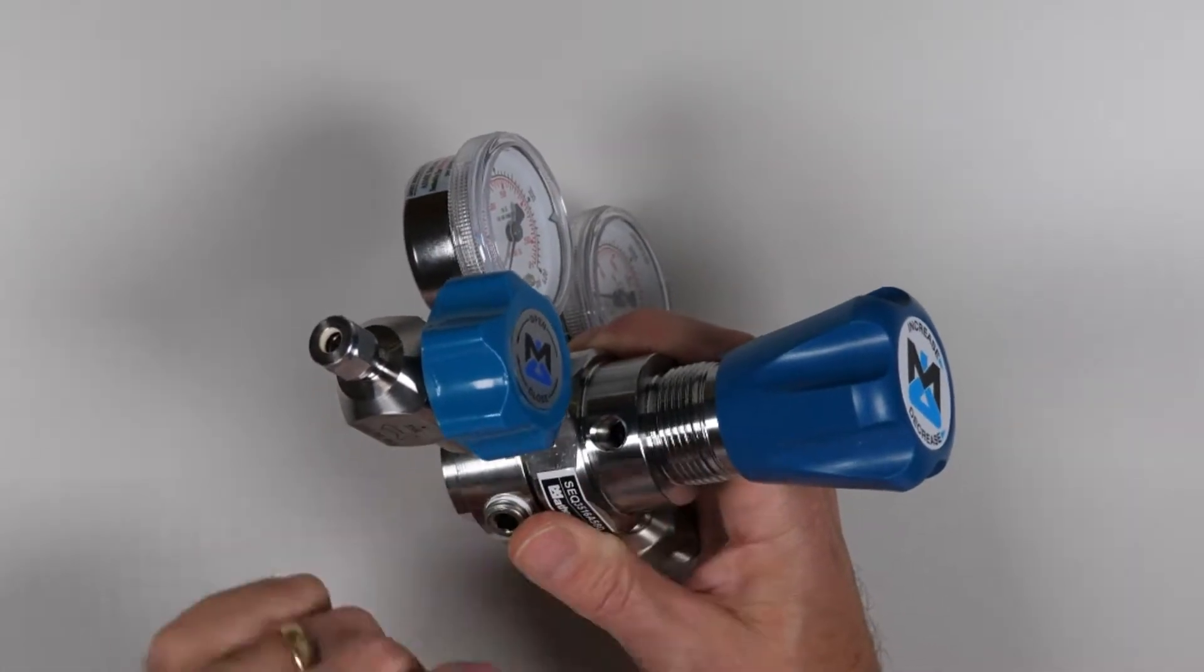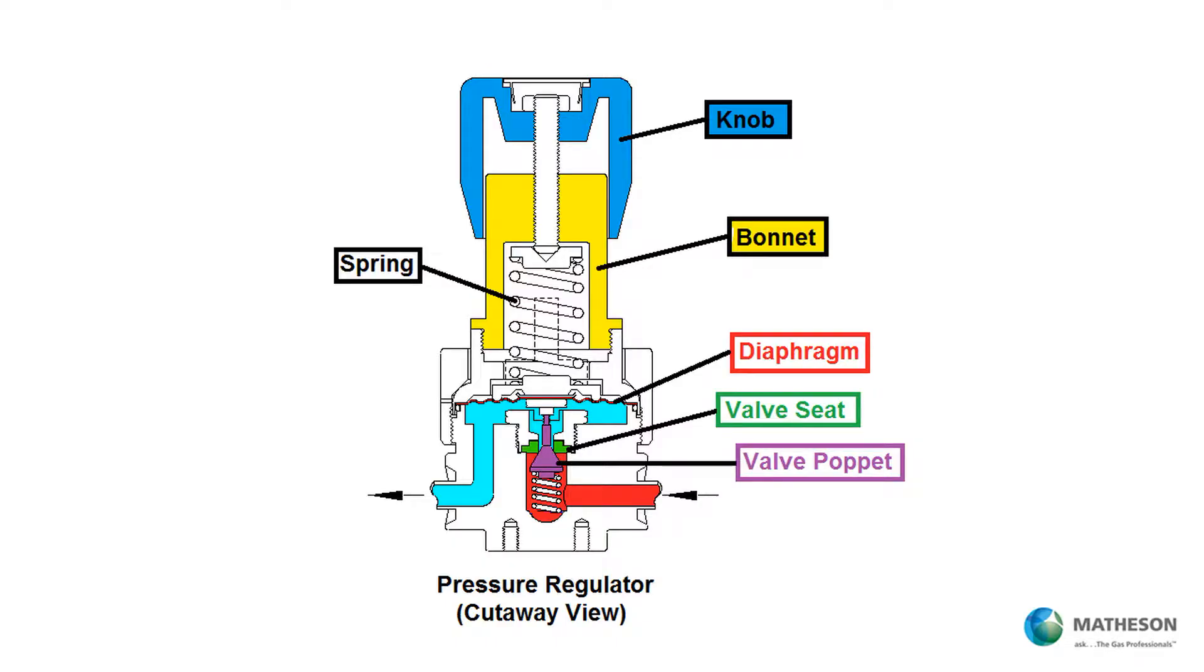This is the bonnet which holds the spring. When the regulator hand knob is turned, the spring is compressed. The spring displaces the diaphragm. The diaphragm then pushes on the valve poppet, causing it to move away from the valve seat. The orifice becomes larger in order to provide the pressure and flow required.